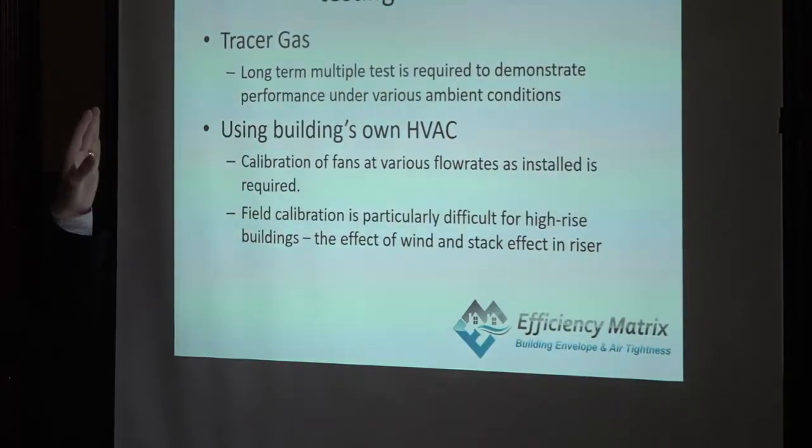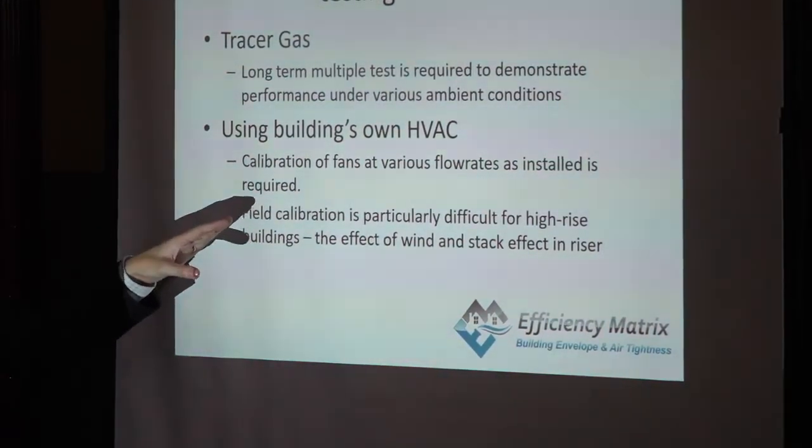Using the building's HVAC system is convenient since you've already paid for it, but it can't give you a quantifiable number with the required accuracy. Most fans are not calibrated — they have a nominal performance. Even if you calibrate a fan before installation, you can't account for the pressure drop from the ductwork. And if you calibrate after installation in the building, the ambient wind will mess things up completely. It's good for indicative performance, but it can't give you a definitive number.